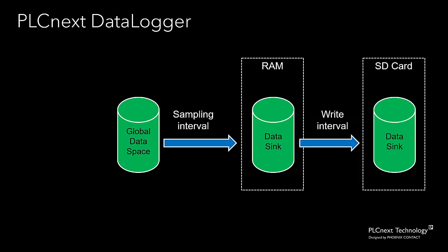It's actually important to realize that the write interval is not actually a time interval. In the PLCnext data logger, the write interval represents a count — a count of the number of records that are accumulated in the in-memory Data Sink before that data is written to the SD card. We would like the write interval to be as high as possible, which means we write to the SD card at the lowest frequency possible. But if we make the write interval too large, that will use up all the available memory in the RAM. So it's a trade-off between those two factors when choosing a write interval for a particular application.